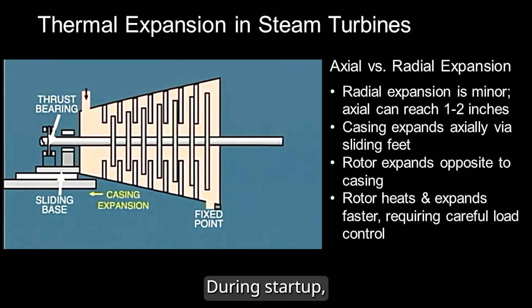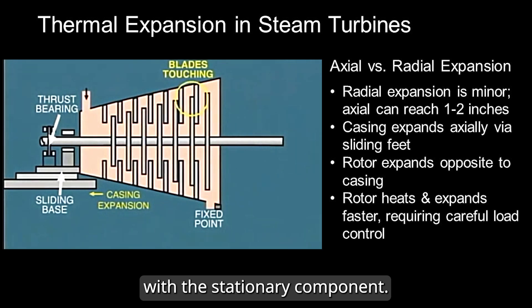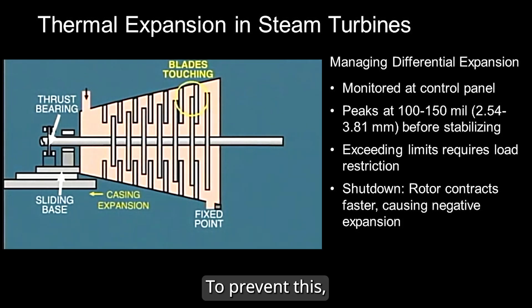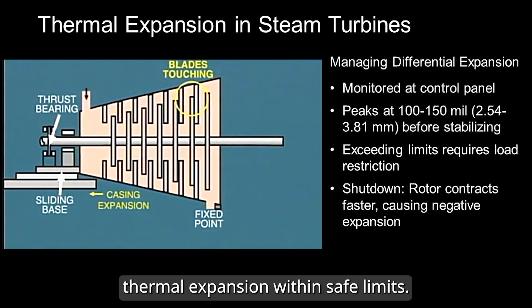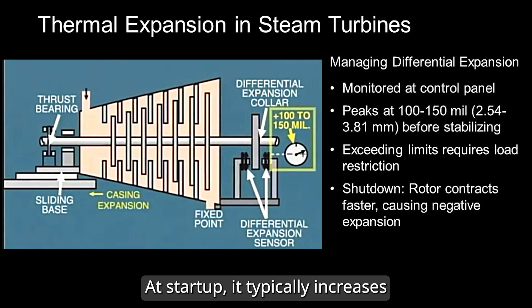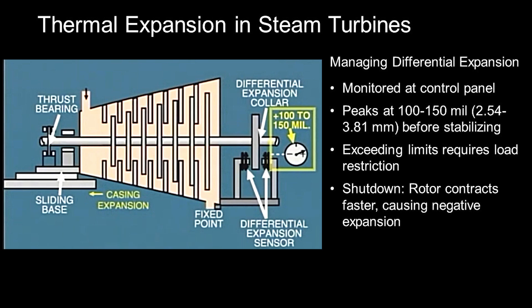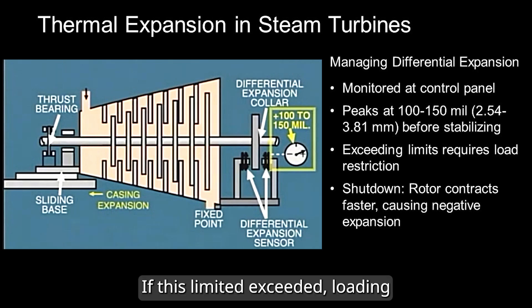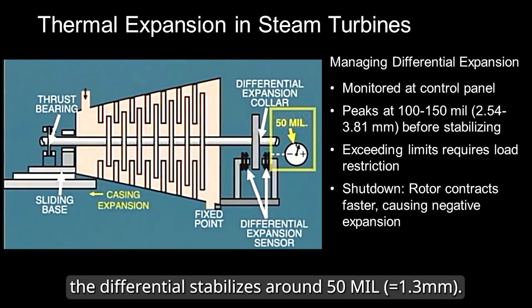During startup, rapid rotor expansion increases the risk of blade contact with the stationary component. To prevent this, load changes must be carefully managed to keep differential thermal expansion within safe limits. At startup, it typically increases to 100 to 150 mils before stabilizing. If this limit is exceeded, loading must be restricted to avoid damage. As the casing continues to expand, the differential stabilizes around 50 mils.